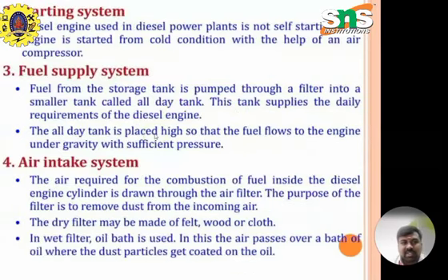A starting system. The diesel engine used in a diesel power plant is not self-starting. The engine is started from the cold condition with the help of an air compressor. The fuel supply system. Fuel from the storage tank is pumped through a filter into a smaller tank. It is called the all-day tank. This tank supplies the daily requirement of the diesel engines. The all-day tank is placed high so that the fuel flows to the engine under gravity with sufficient pressure.